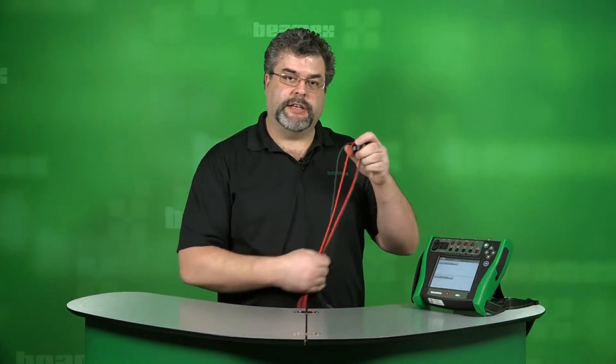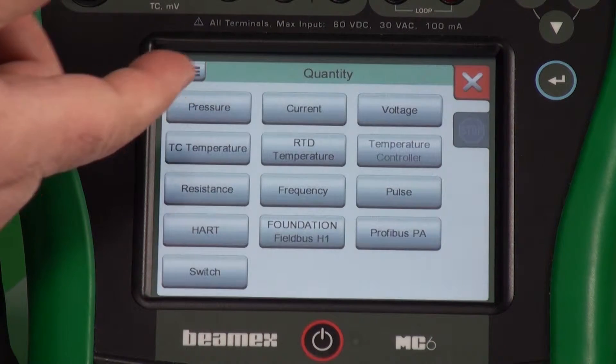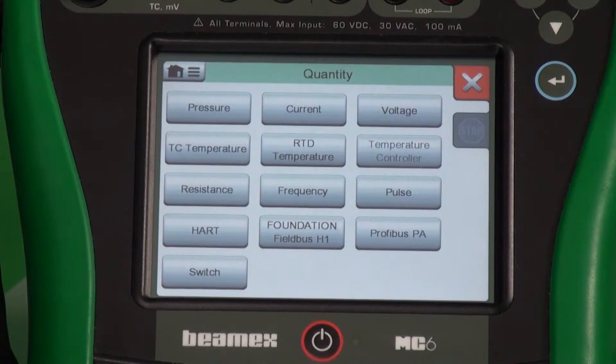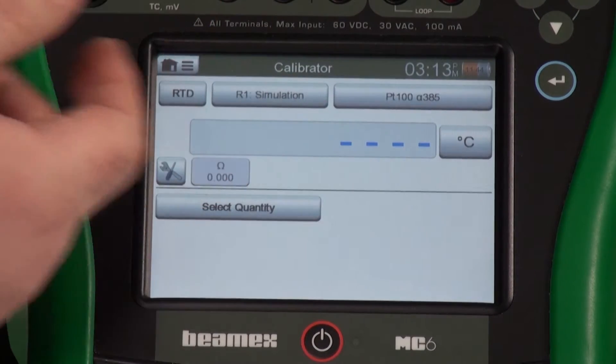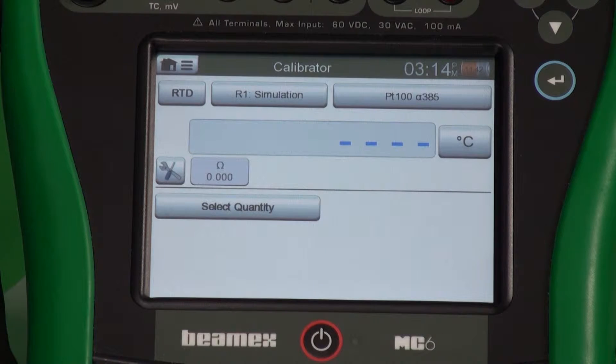Let's take this as an example. I've got an RTD temperature transmitter, so I need to simulate temperature. I tend to put the input on the top, so we'll select quantity. My input in this case is RTD temperature. Now I'm simulating instead of measuring, so I do want simulate, and my type is a Platinum 100 385, so that's perfect.